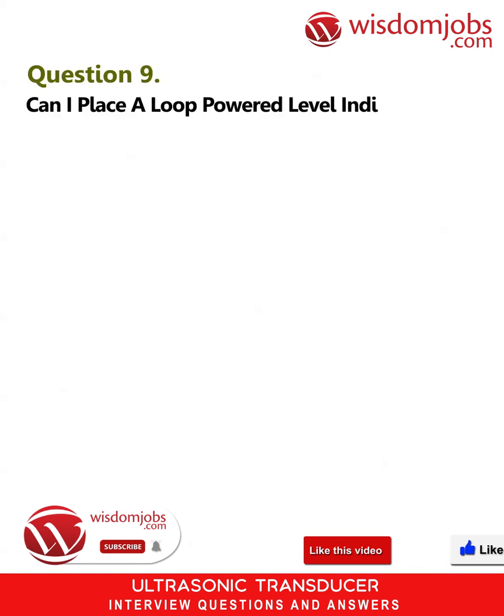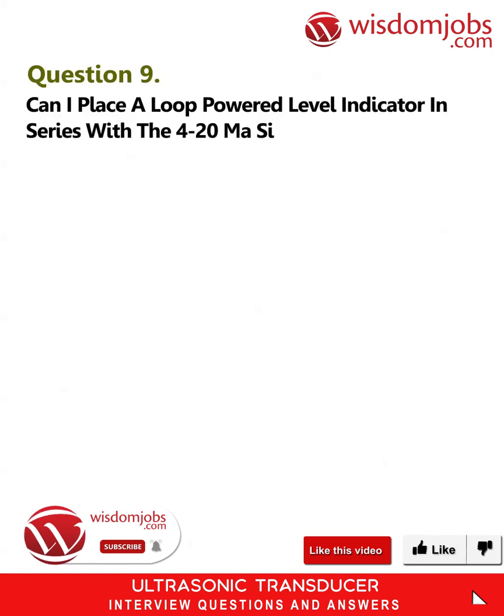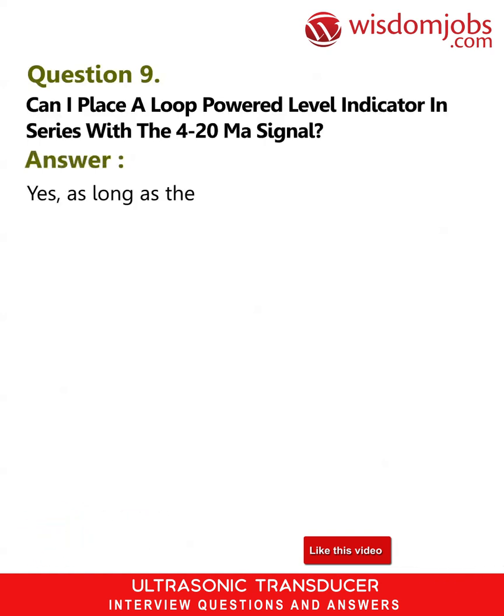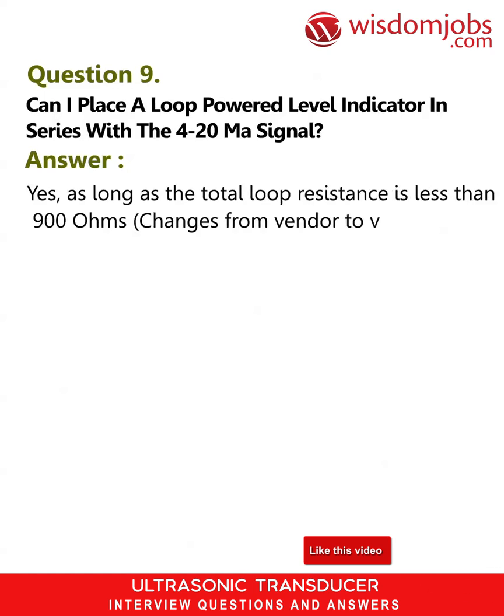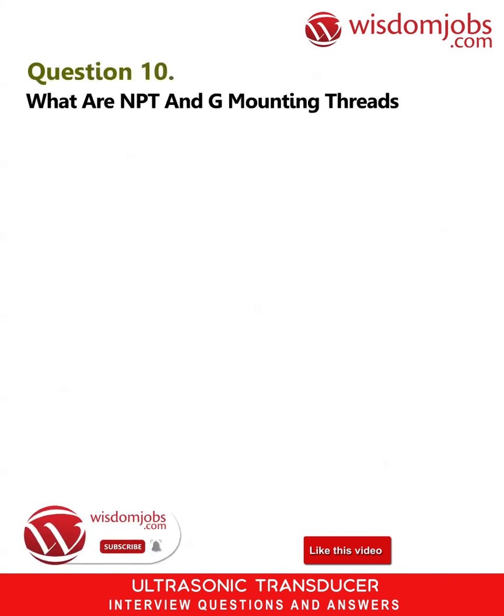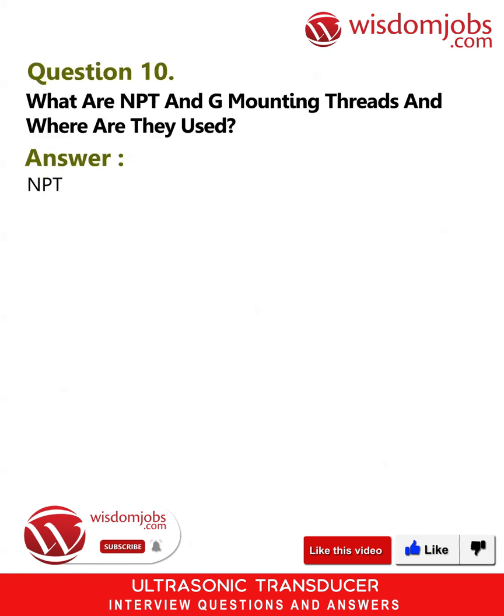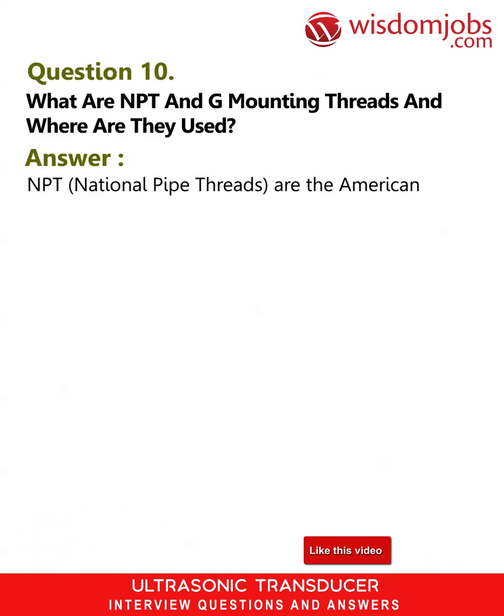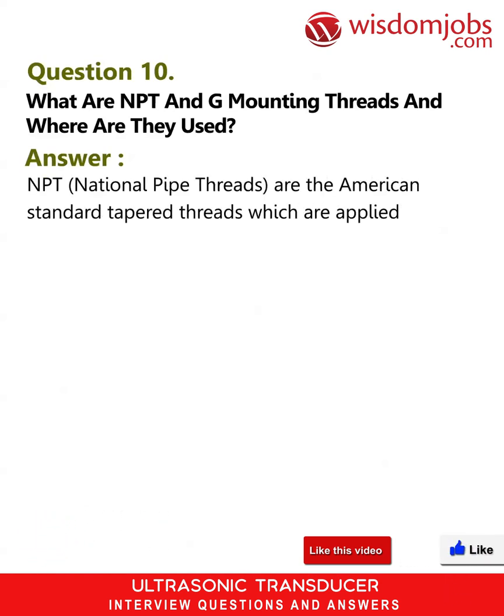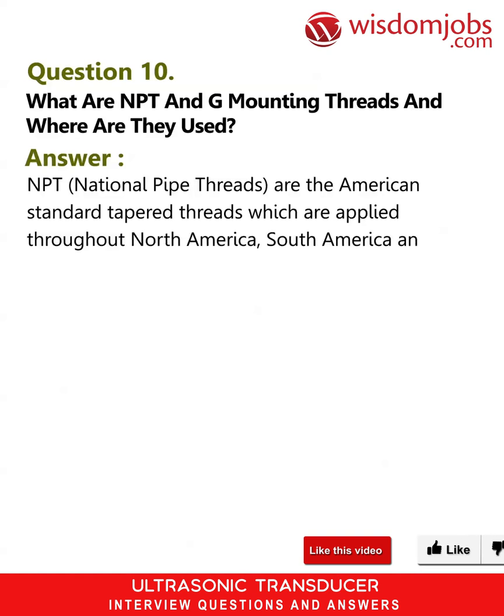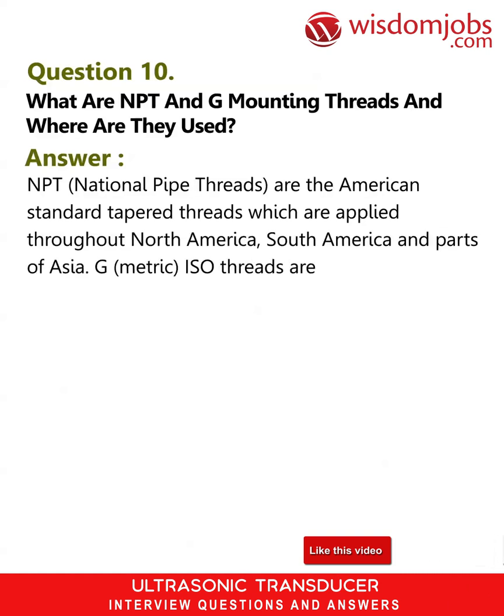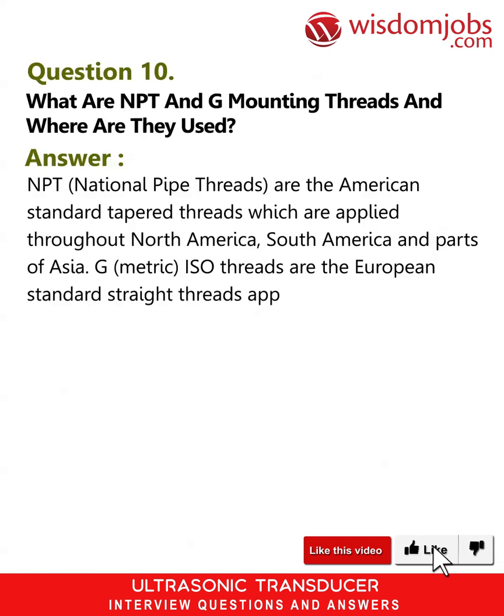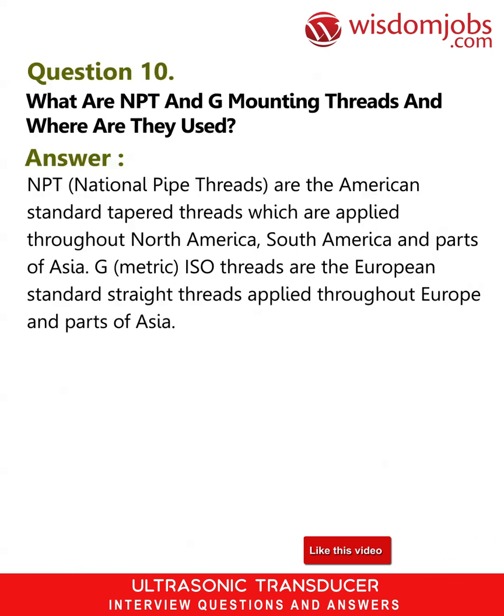Question 9. Can I place a loop-powered level indicator in series with the 4 to 20 mA signal? Answer. Yes, as long as the total loop resistance is less than 900 ohms. Changes from vendor to vendor. Question 10. What are NPT and G mounting threads and where are they used? Answer. National pipe threads are the American standard tapered threads which are applied throughout North America, South America and parts of Asia. G metric ISO threads are the European standard straight threads applied throughout Europe and parts of Asia.